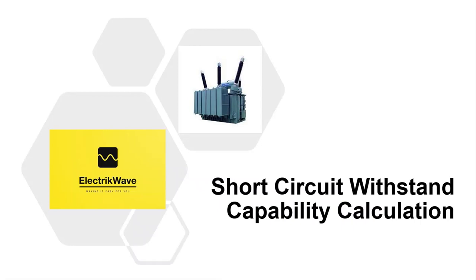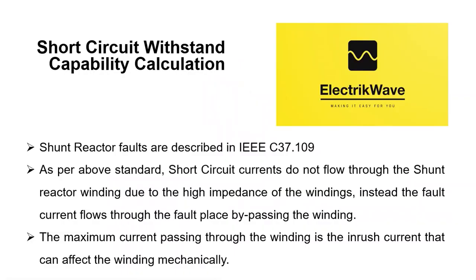Now let's start with a discussion about the short circuit withstand capability calculation for 120 MVAR, 400 kV shunt reactor. Shunt reactor faults are described in IEEE C37.109. As per the above standard, short circuit currents do not flow through the shunt reactor winding due to the high impedance of the windings; instead the fault current flows through the fault place bypassing the winding. The maximum current passing through the winding is the inrush current, which can affect the winding mechanically.